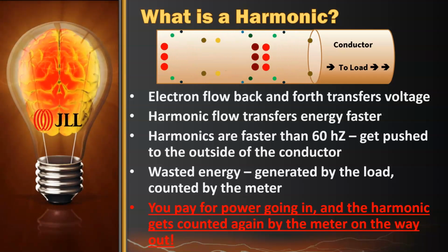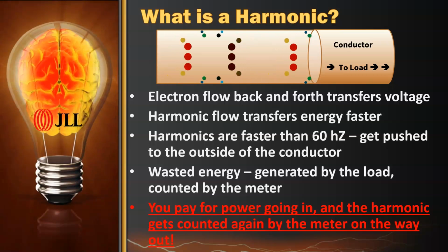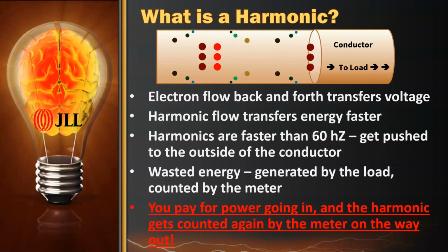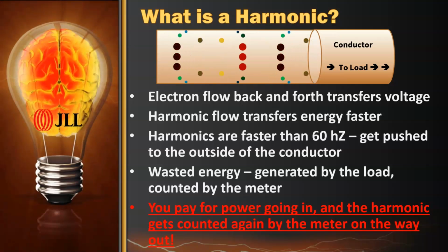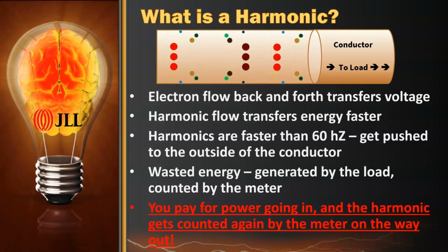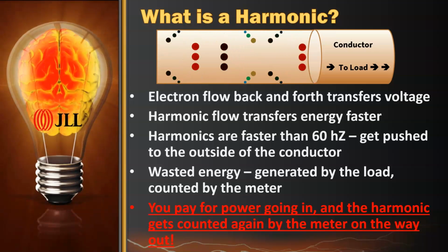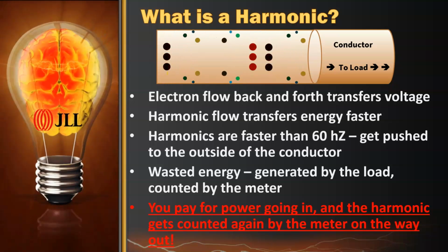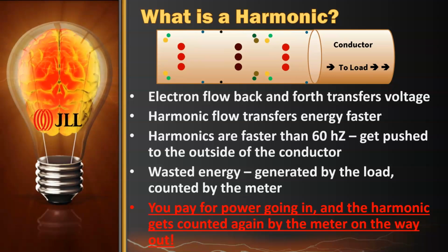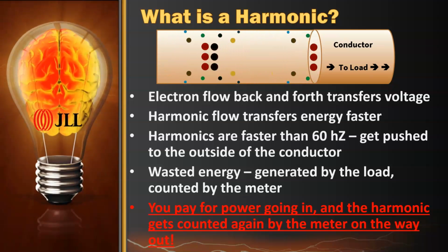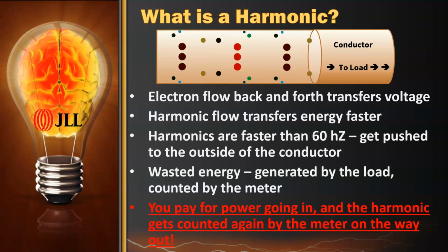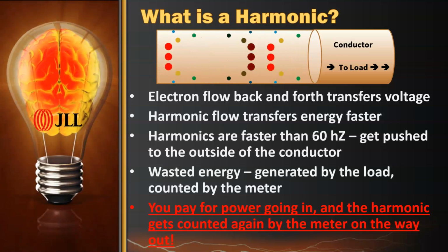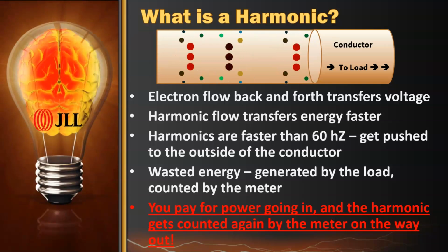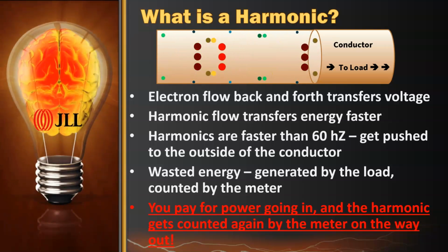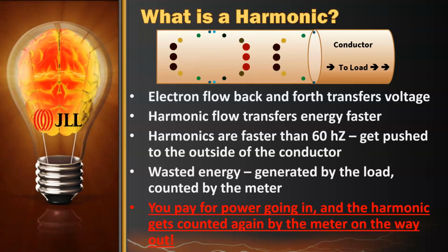Of course, this also heats up the conductor, as you can imagine. You're doing some physical damage to the conductor itself, so it heats it up. And it heats up the transformer, heats up the starters, heats up contactors. Everything gets heated up by this weird sort of motion. It's not really useful energy. Harmonic, it doesn't do an awful lot of work because all of the devices that are in the system are made to operate with the 60 hertz waveform. So it kind of just runs back and forth and annoys everybody.